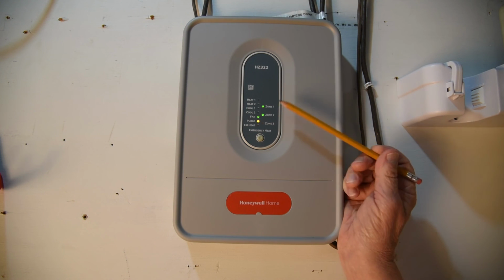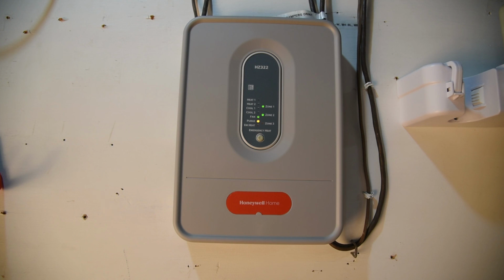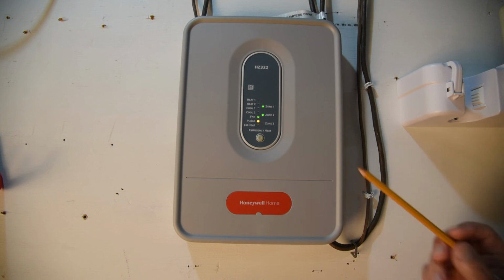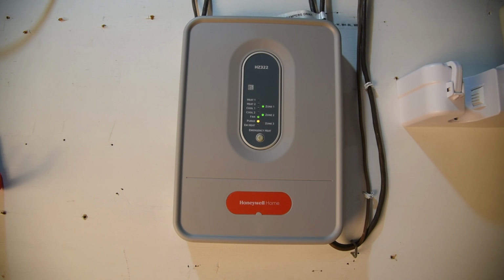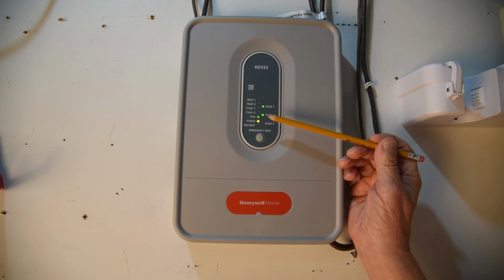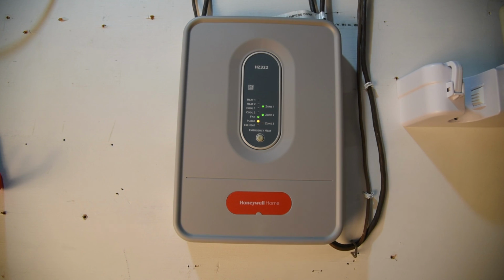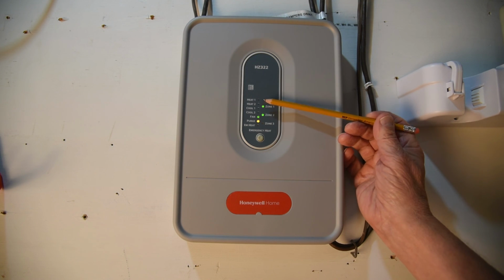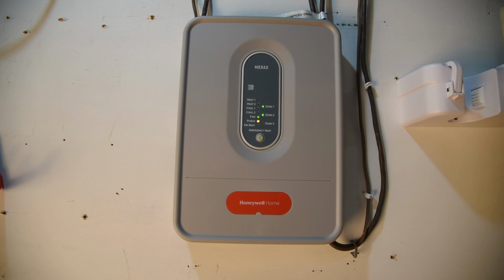Here you can see no cooling light, zone 1 and zone 2, because once it takes that off, I have it set to open the dampers. The dampers will be opening now. The fan is on to purge. This will last for 5 minutes, and then these 2 lights will go off, everything will turn off. I'm not going to run the heat during the summer, but heat would operate similarly. You might get both stages coming on, and that's pretty much the operation of the zone panel.